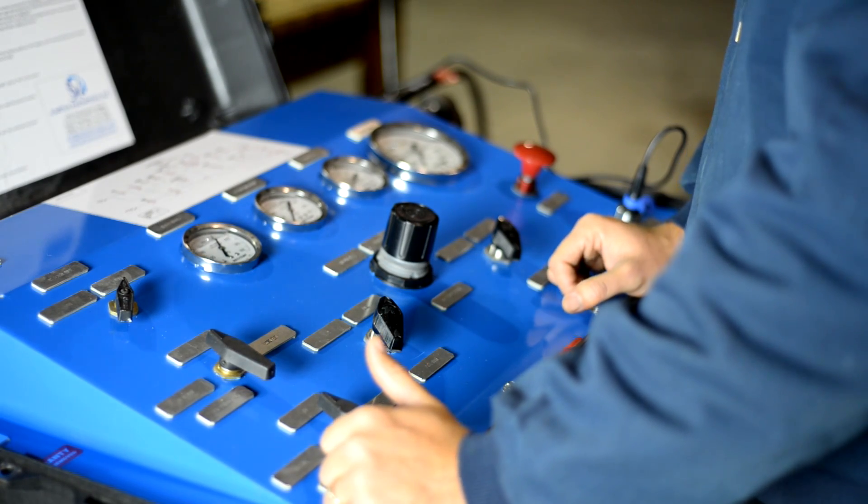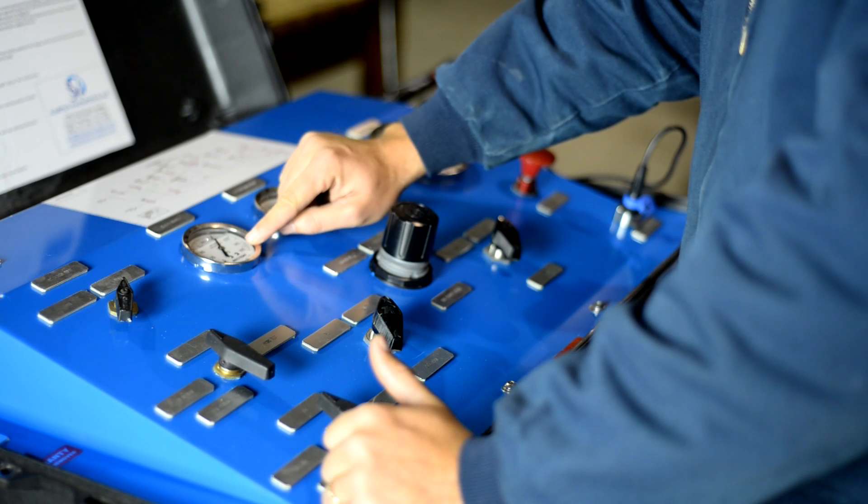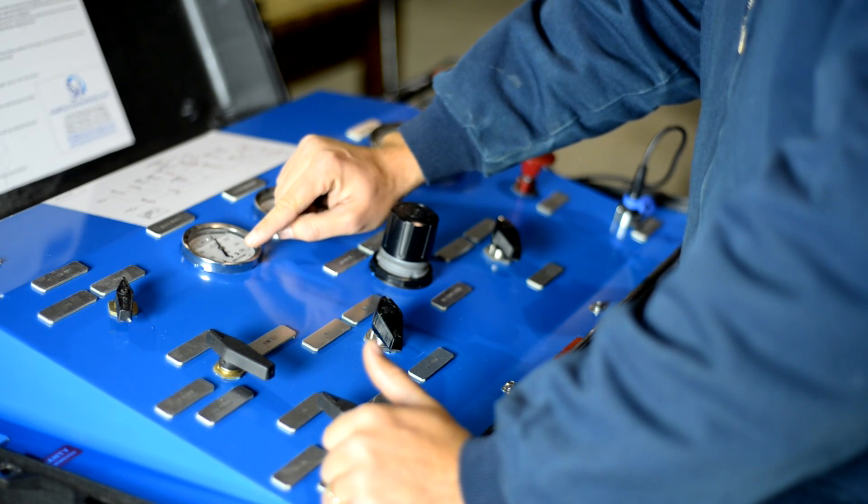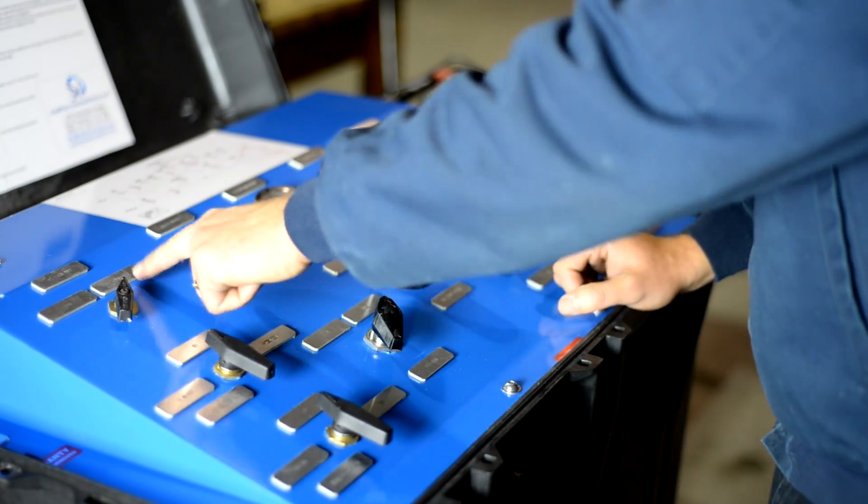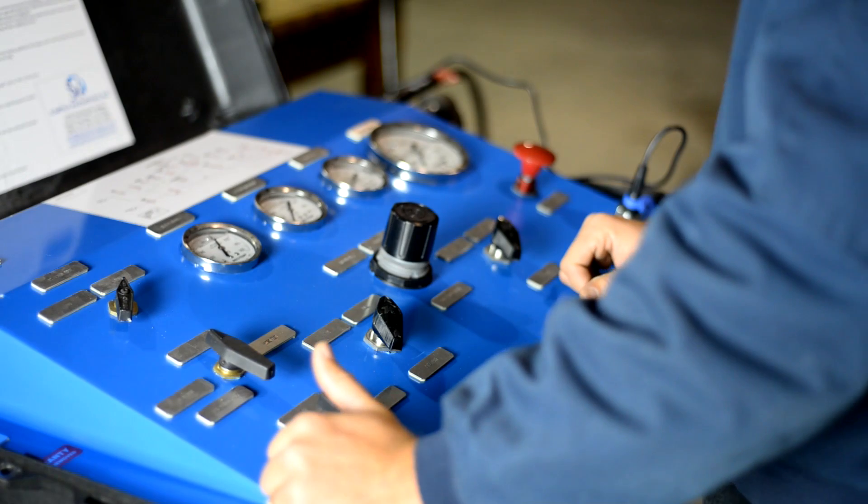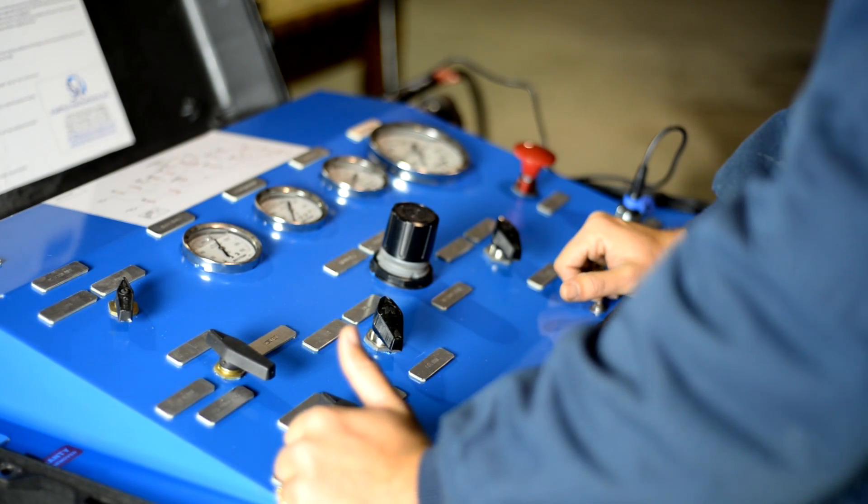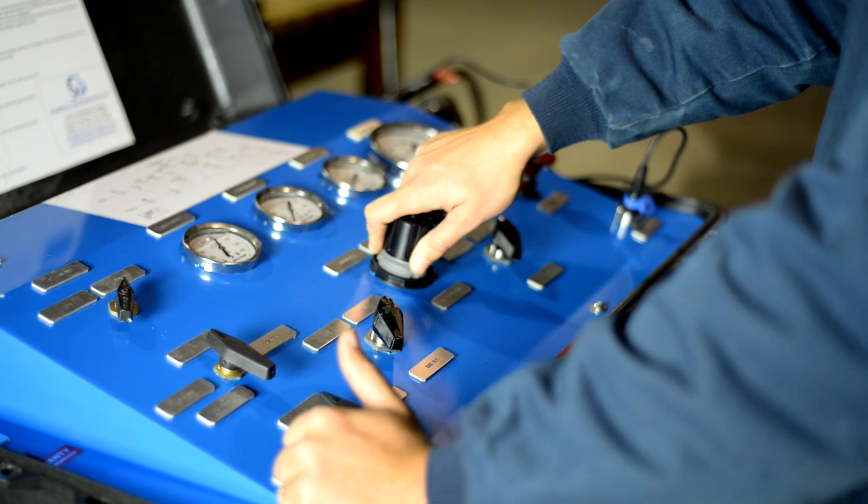Prior to testing, check the air inlet pressure gauge to ensure that there is pressure in the system. Make sure that the valves are all in closed position. Ensure that the test pressure control has been turned counter-clockwise to stop to ensure there is no pressure on the system.